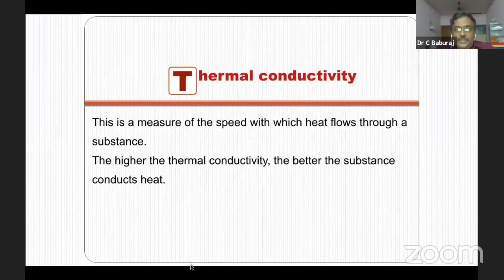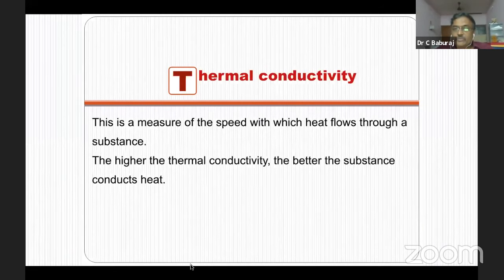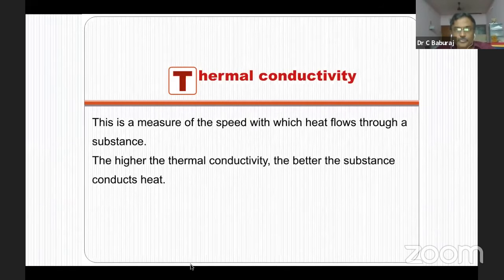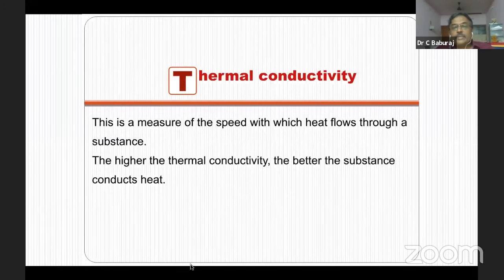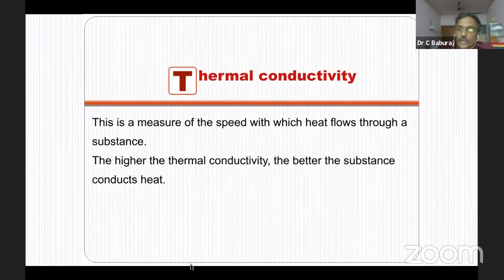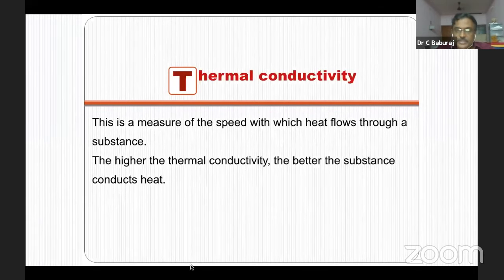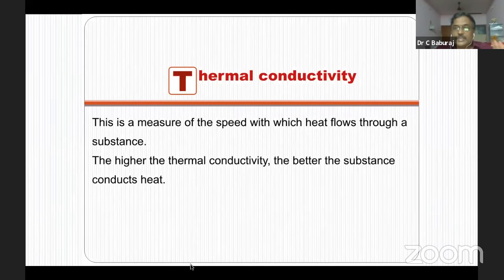The last part of physical principles is thermal conductivity — a measure of the speed with which heat flows through a substance. The vaporizer is made up of copper, and if the thermal conductivity is good, the material can transmit heat from outside into the liquid so that vaporization can be constant. So far we have learned SVP, boiling point, heat of vaporization, specific heat, and thermal conductivity — the five basic physical principles concerned with vaporizers.